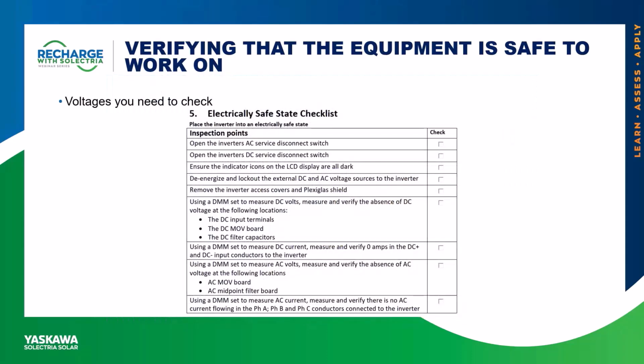Again, just to review, going back to our list: we opened all the AC and DC services. We made sure that none of the lights and panels are still on, everything's off. We located the other external sources like our combiners, and locked and tagged out those as well. We removed the inverter covers if there's any additional shielding internally. And then we verified the absence of both the AC and DC voltages as well as the currents.